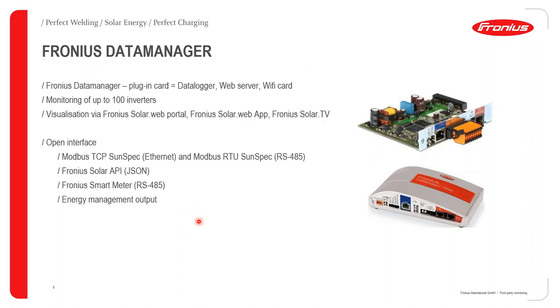The Data Manager is basically a plug-in card that serves as a data logger, web server, and Wi-Fi card. It can monitor up to 100 inverters, and you can achieve visualization via the Fronius Solar Web Portal, Fronius Solar Web App, and Fronius Solar TV. It has open interfaces including Modbus TCP and Modbus RTU.